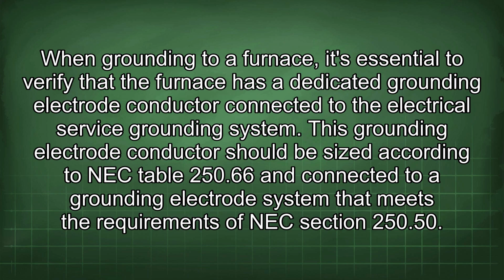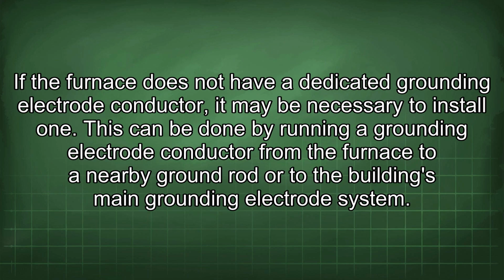When grounding to a furnace, it's essential to verify that the furnace has a dedicated grounding electrode conductor connected to the electrical service grounding system. This grounding electrode conductor should be sized according to NEC Table 250.66 and connected to a grounding electrode system that meets the requirements of NEC Section 250.50. If the furnace does not have a dedicated grounding electrode conductor, it may be necessary to install one.